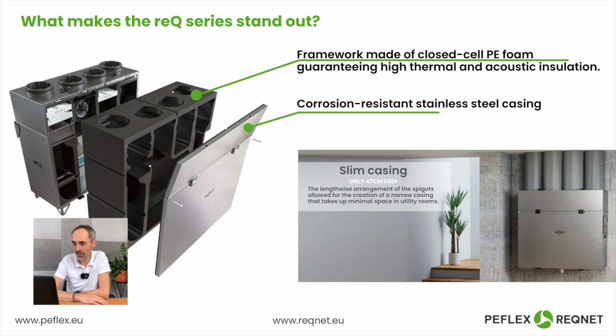The internal frame. The internal part of the heat recovery unit is made of closed cell foam, which provides proper thermal and acoustic insulation, but is also resistant to water and moisture. So even if some condensation were to occur inside the heat recovery unit, it doesn't affect the foam or the internal structure in any way, meaning the internal closed cell foam remains unaffected.